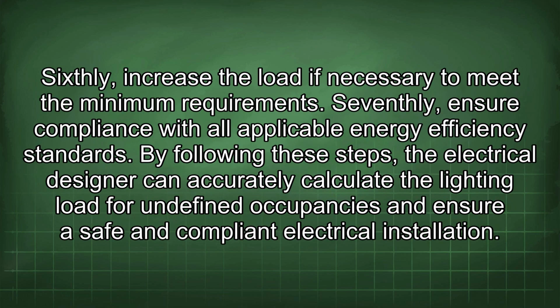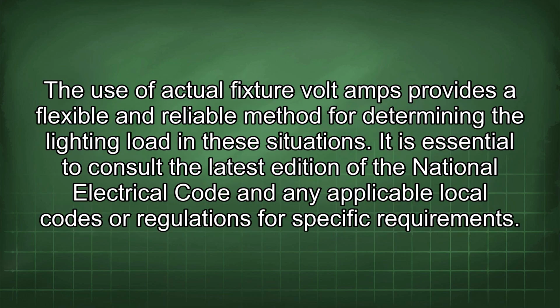Sixthly, increase the load if necessary to meet the minimum requirements. Seventhly, ensure compliance with all applicable energy efficiency standards. By following these steps, the electrical designer can accurately calculate the lighting load for undefined occupancies and ensure a safe and compliant electrical installation. The use of actual fixture volt amps provides a flexible and reliable method for determining the lighting load in these situations.